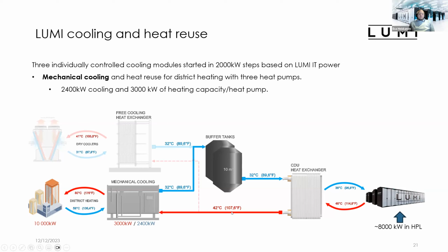So we are having 42 Celsius inlet from the Lumi, which is cooled down to 32 degrees Celsius using the heat pumps, and it's running through the buffer tanks and going to the CDU heat exchanger, and it's running up to 38 degrees in the Lumi's internal cooling loop, which is called the secondary cooling loop.